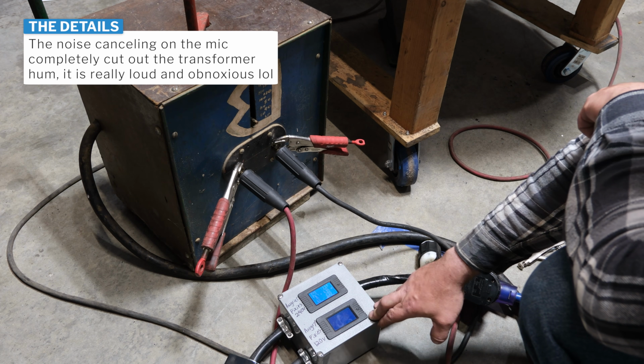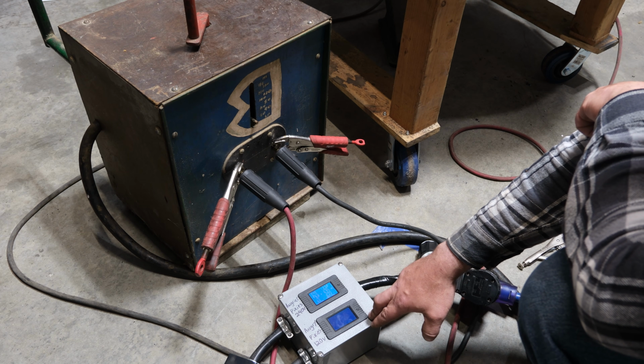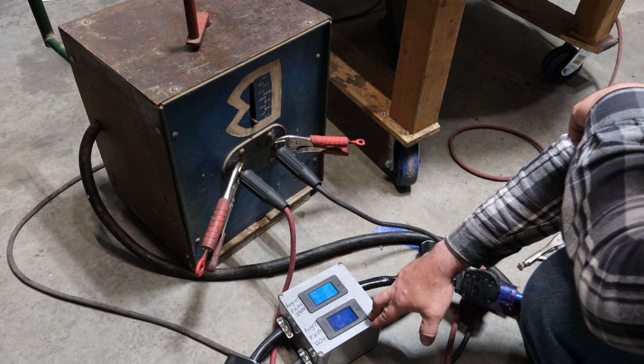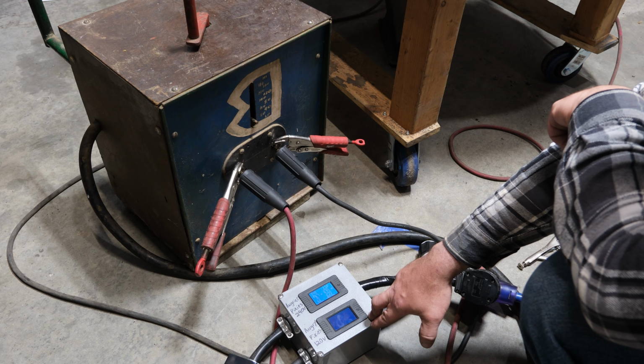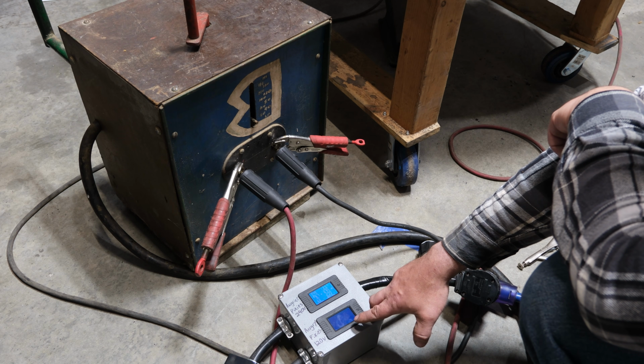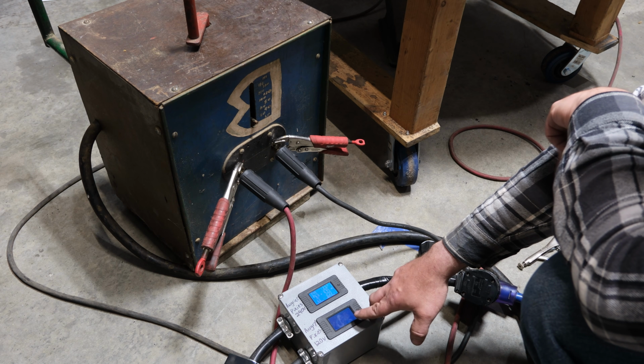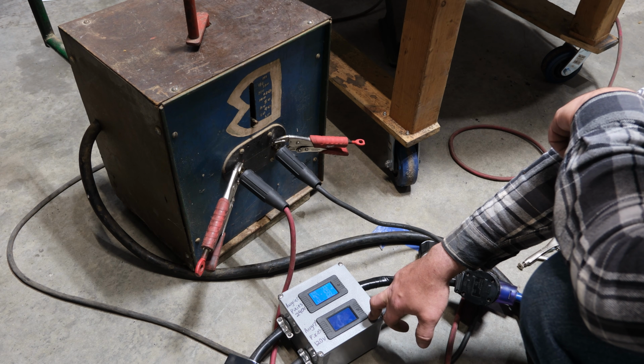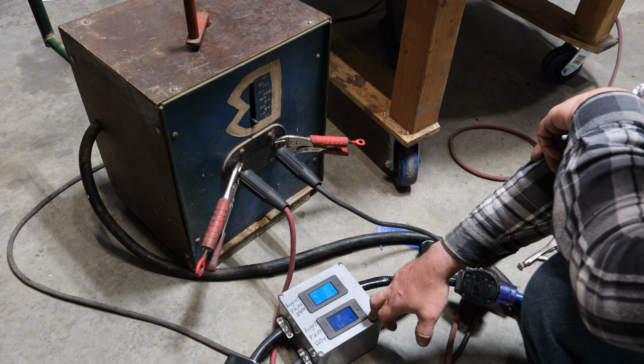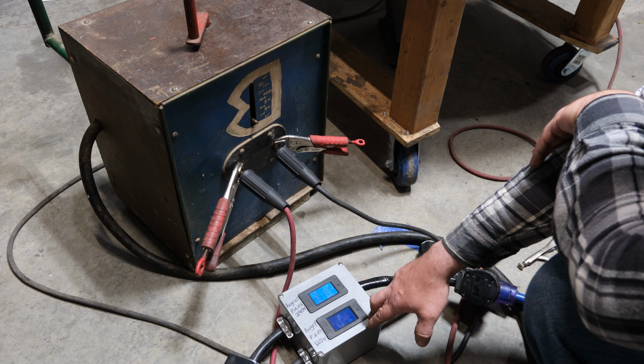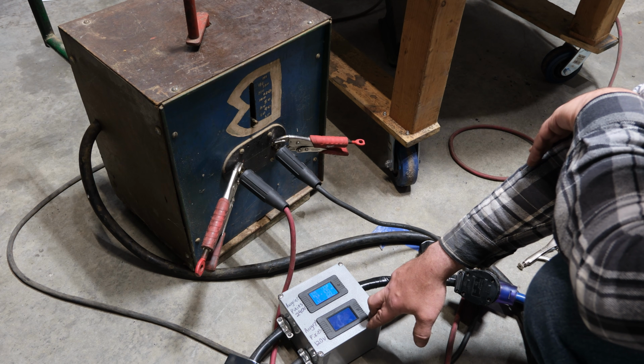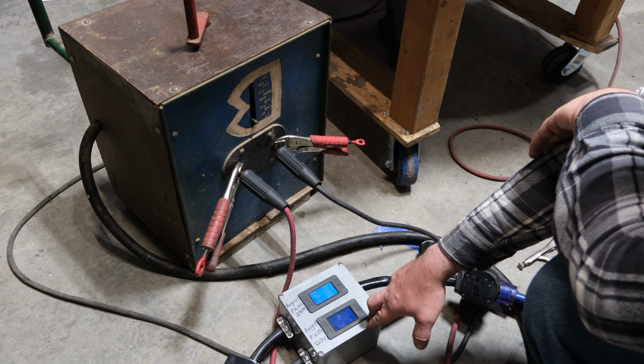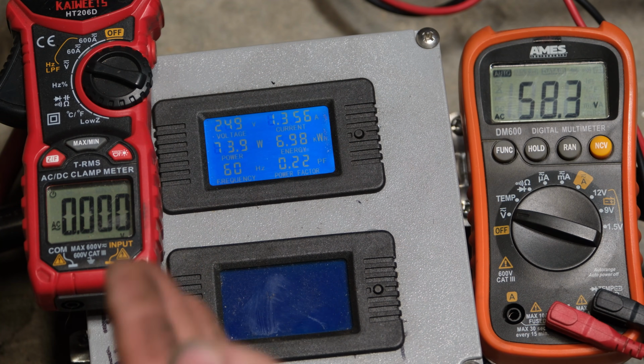But anyways, it's only pulling about 1.3 amps at idle with no load on it. So as far as I can tell, everything's looking pretty good. There really isn't any kind of short that would be concerning. So that's all looking good. The power factor at idle is 0.22, so pretty atrocious, as I would have expected. And this has no obvious power factor correction, no capacitors. I mean, this thing is as simple as you can get. It's a literal transformer out of something that someone repurposed for welding. So we're clear as mud here.